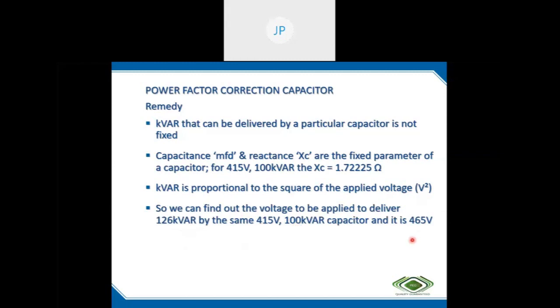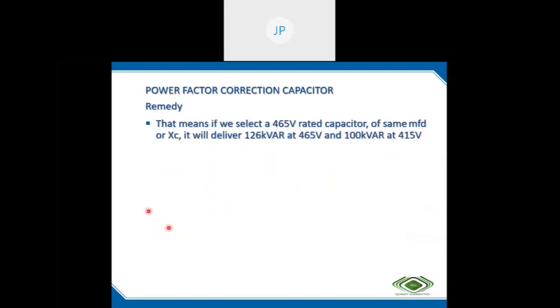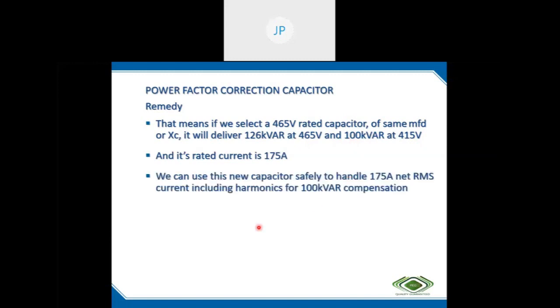That means if we purchase or specify a capacitor of the same MFD and same Xc with a voltage rating of 465 volt, its delivered kVAr will be 126, but its current rating will be 175. If we select a 465 volt capacitor, it will deliver 126 kVAr at 465 volt, and since we are applying only 415 volt, we will get only 100 kVAr, and its rated current is 175 amps. We can use this capacitor safely to handle 175, and it will deliver 100.